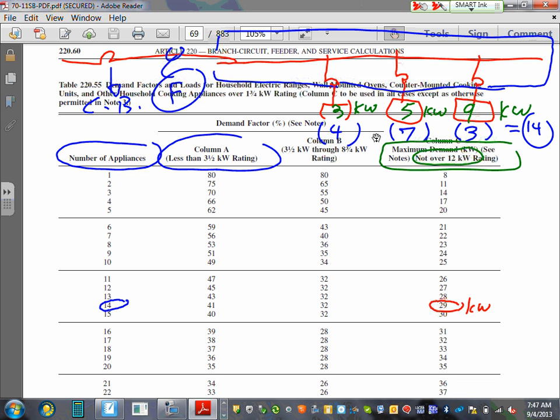Okay, now, any question guys about these? Your first question you're going to ask yourself, are they less than 12? Yep. How many of them do you have? 14. What's my demand? 29. Now, the second question you're going to ask yourself, does column A or column B apply to any one of them? Did you guys hear me? The rule first is you go 29. Now, the code allows you to go even deeper, lower than 29. Deeper and lower than 29. So after you get the 29, you have to go check something else.